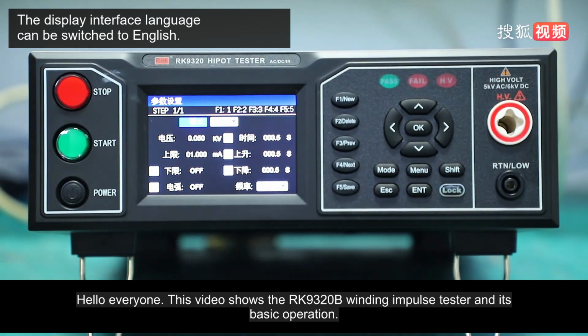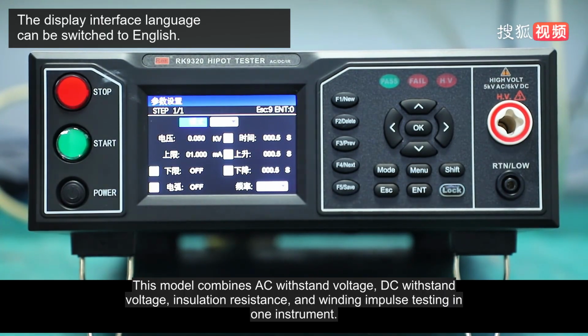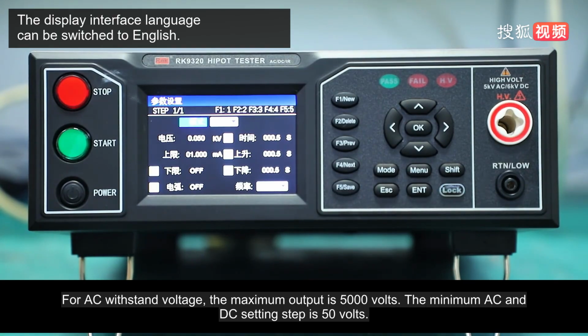Hello everyone. This video shows the RK9320B winding impulse tester and its basic operation. This model combines AC withstand voltage, DC withstand voltage, insulation resistance, and winding impulse testing in one instrument. For AC withstand voltage, the maximum output is 5,000 volts. The minimum AC and DC setting step is 50 volts.